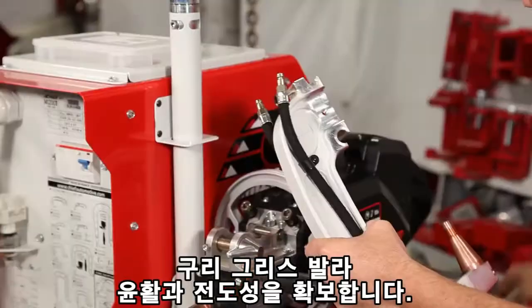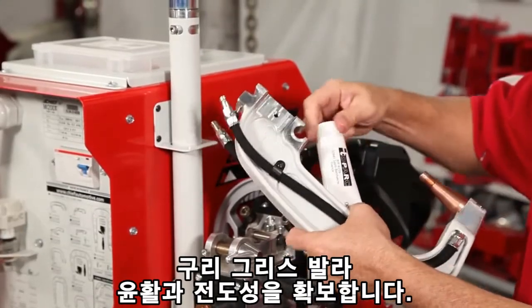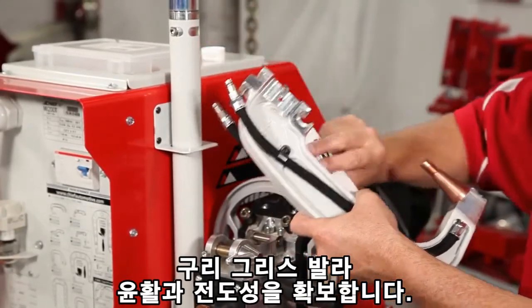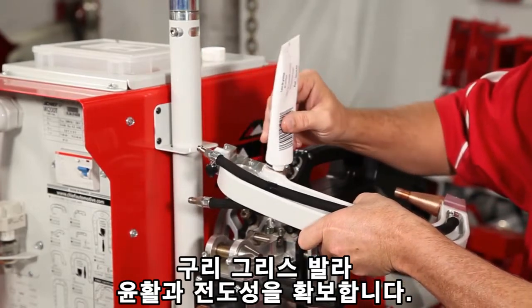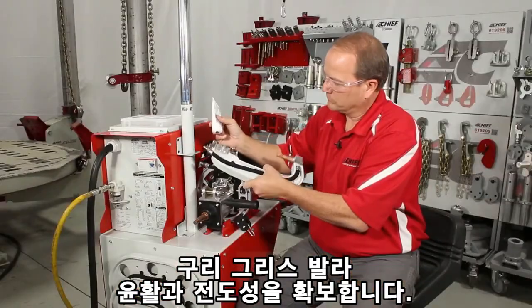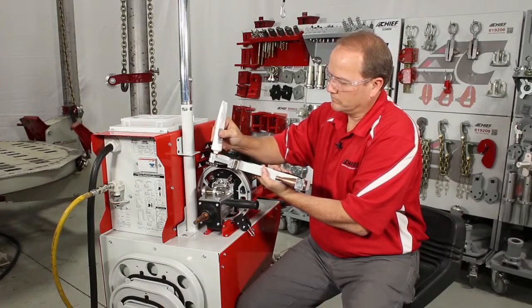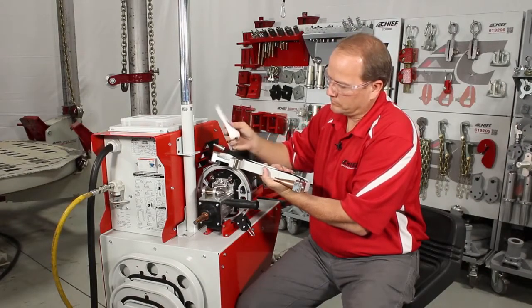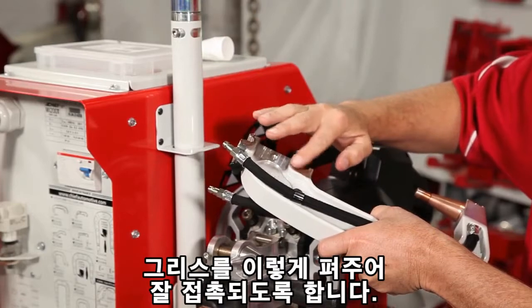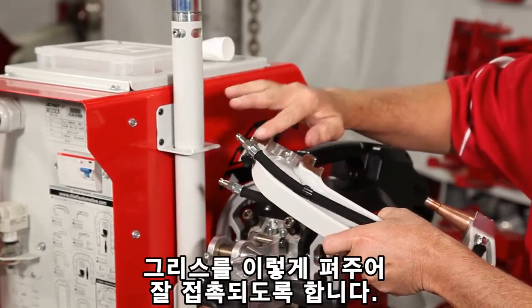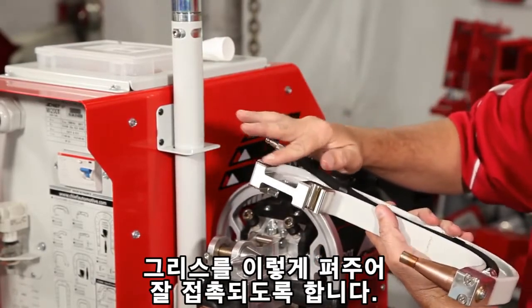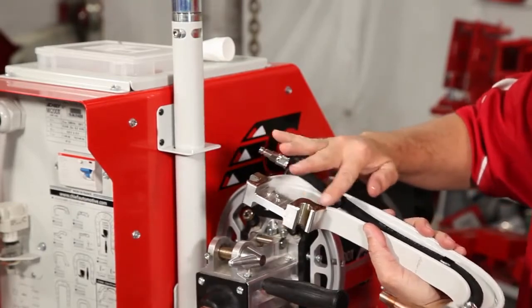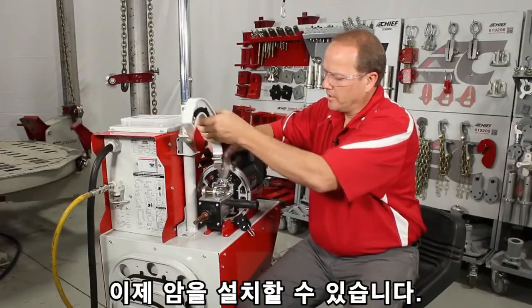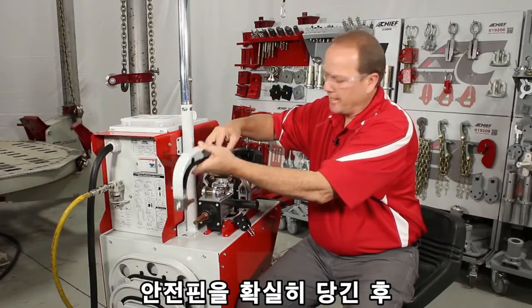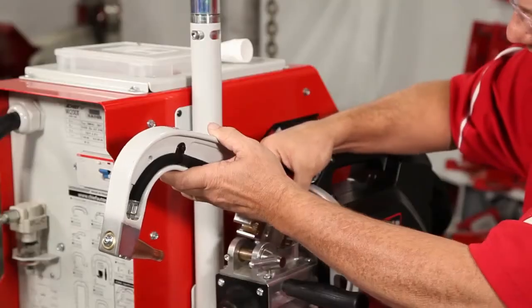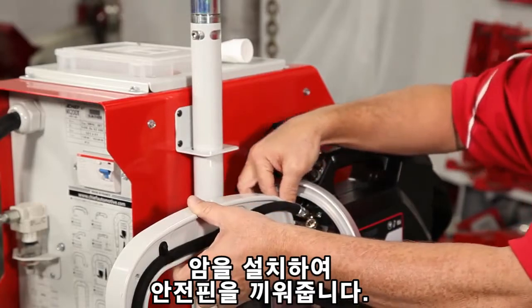Before placing the arm in, we want to make sure that we put a copper grease on here for lubricant and conductivity. We're just smearing the grease, making sure we have good contact on there. Then we can install the arm, making sure that the safety latch is up. Install the arm, drop it down.